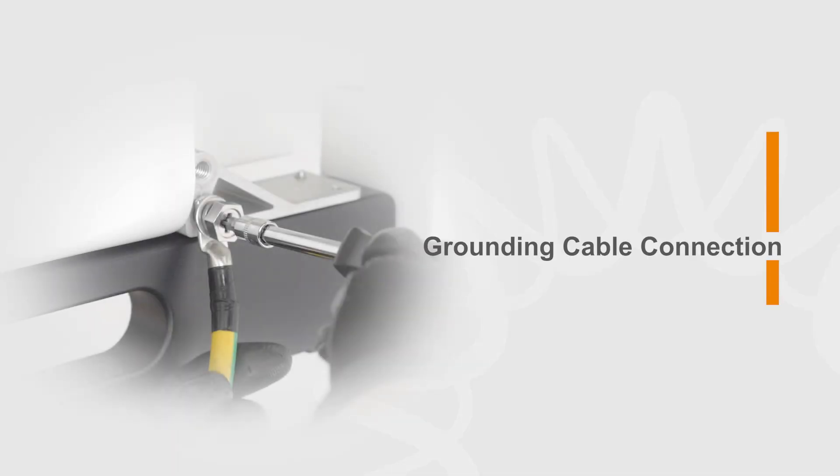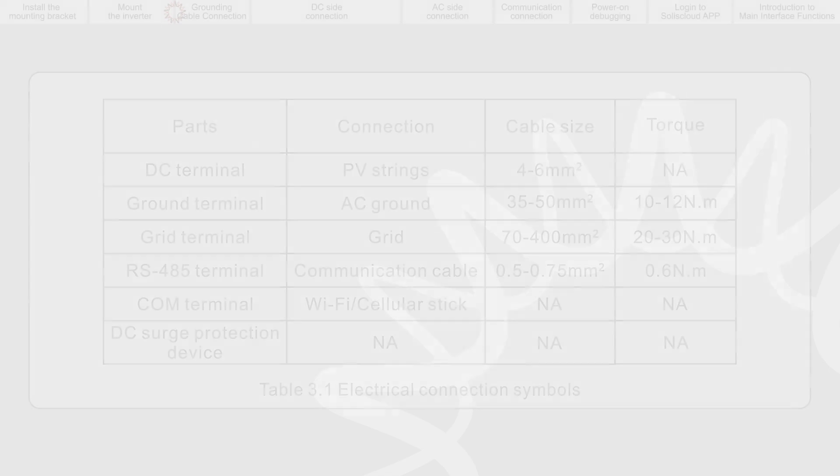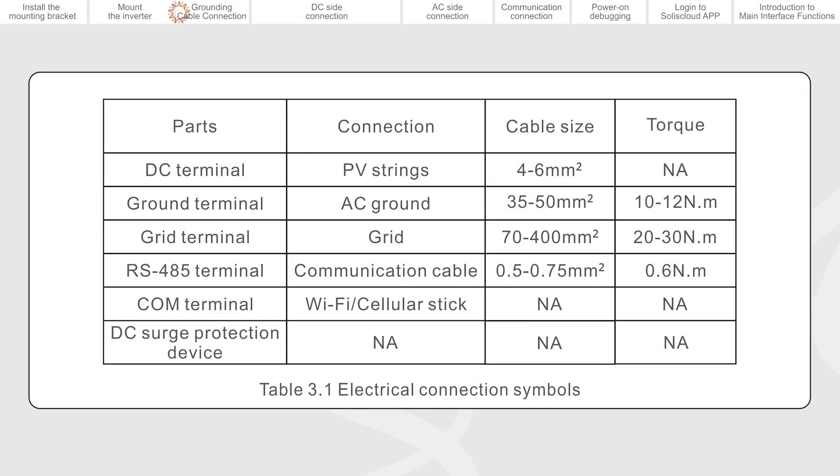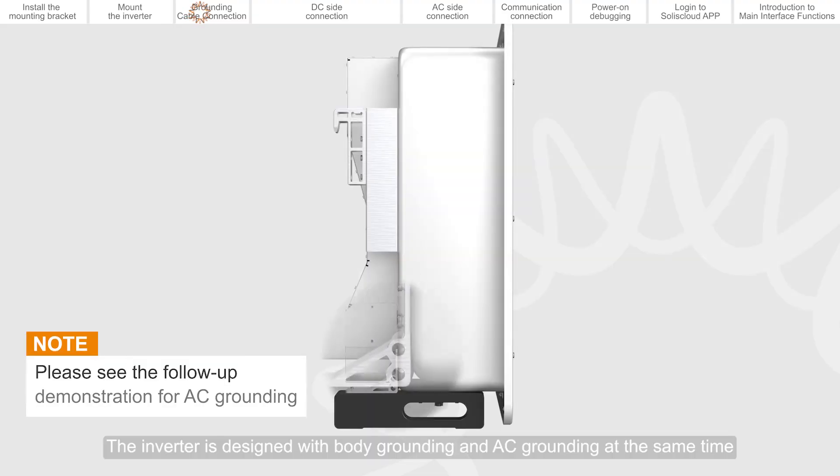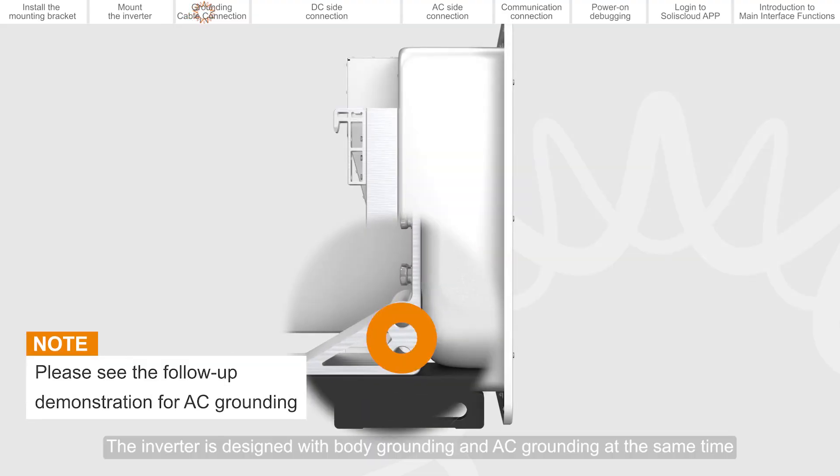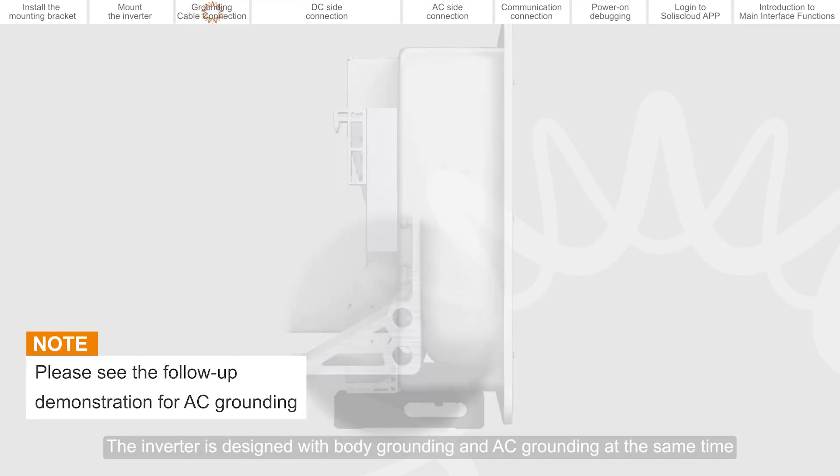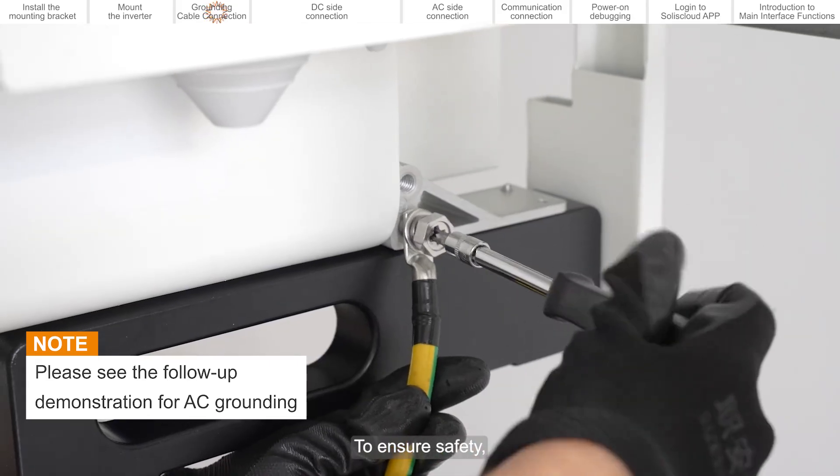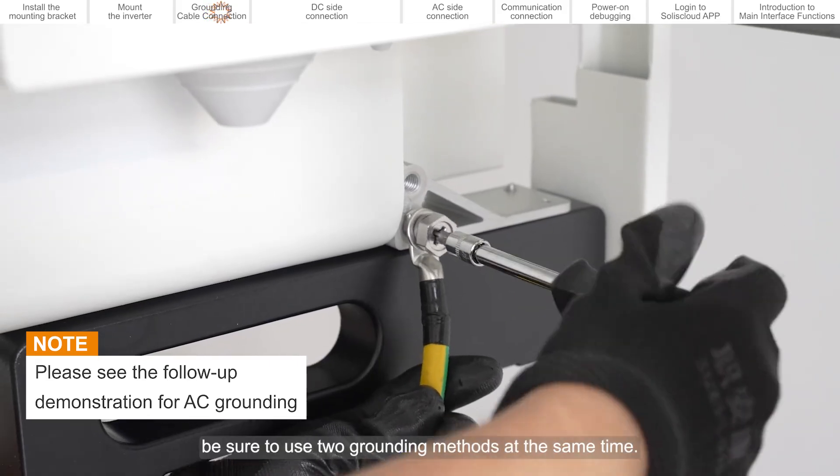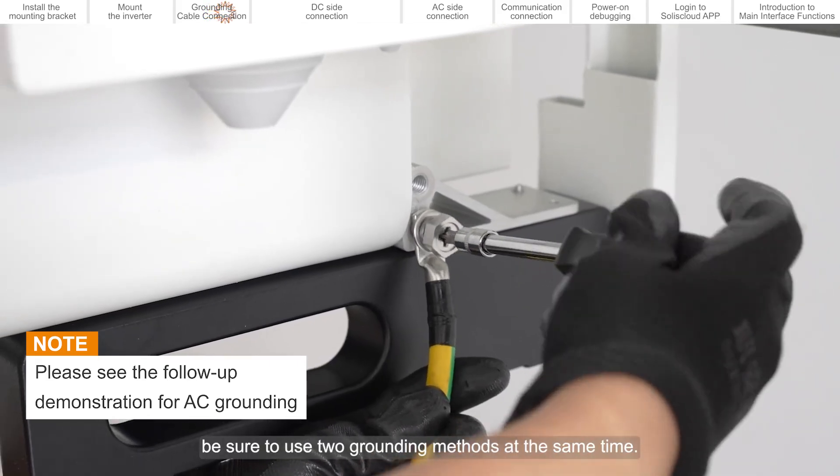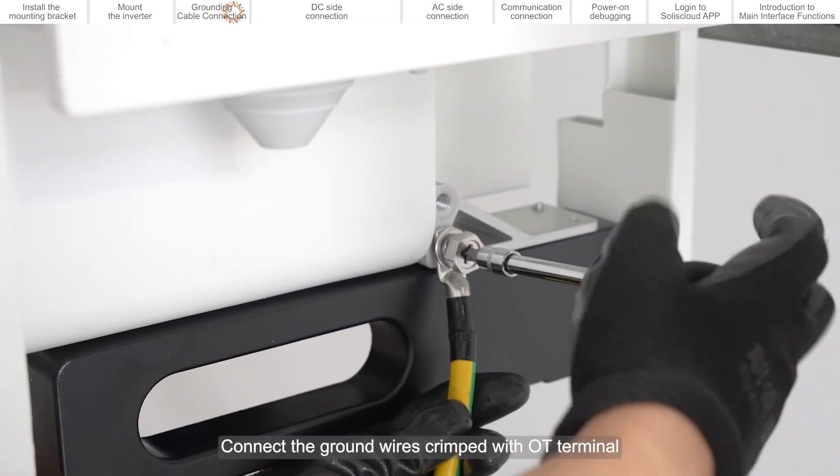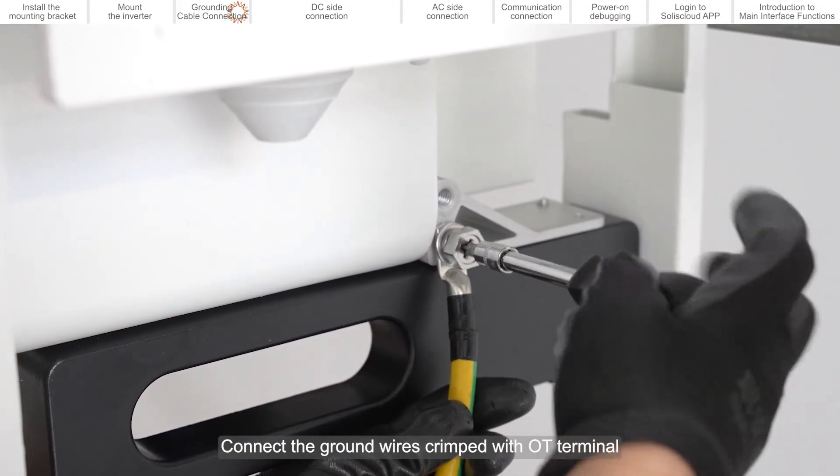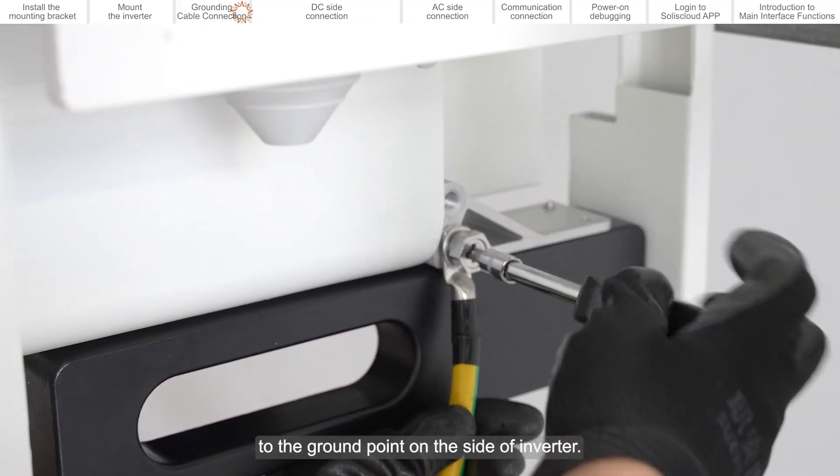Grounding cable connection. The recommended wire diameter for each cable is shown in the figure. The inverter is designed with body grounding and AC grounding at the same time to ensure safety. Be sure to use two grounding methods at the same time. Connect the ground wires crimped with OT terminal to the ground point on the side of inverter.